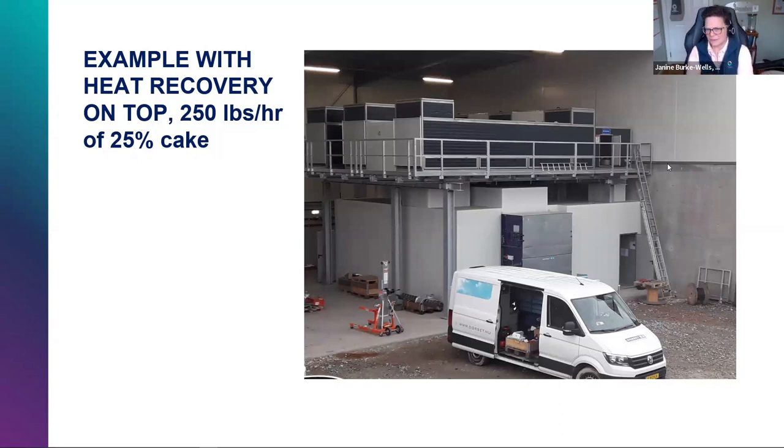Question: what kind of maintenance time should be estimated? About a man-week per year. The whole systems are designed to operate around 5,000 hours per year, which allows enough additional time for maintenance. Routine maintenance is just lubrication of grease fittings and similar tasks. About once a year it's a little more involved — some cleaning, tightening of chain drive systems, and things like that.